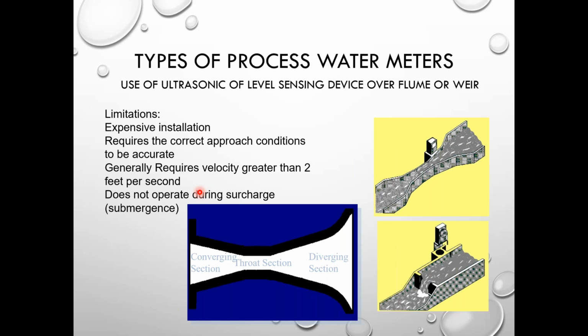So the oldest style of monitoring flow is your flume and weir, and basically flume and weir uses what we call a primary device, where it's calibrated and there's a restriction placed in that open channel that has a known head to flow relationship, right? In other words, the primary device is proportional to the head and the level of flow that's in there. So the methods to obtain level in your primary device have traditionally been rulers, floats, bubblers, differential pressure sensors, and ultrasonic sensors.